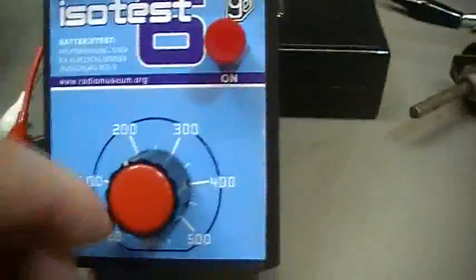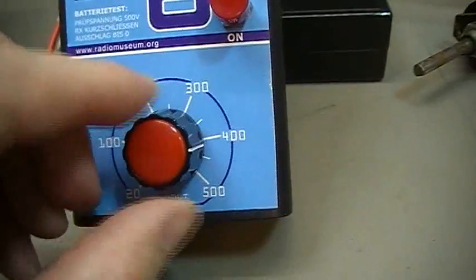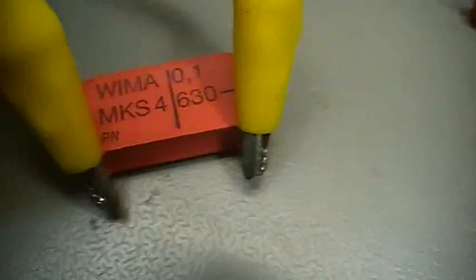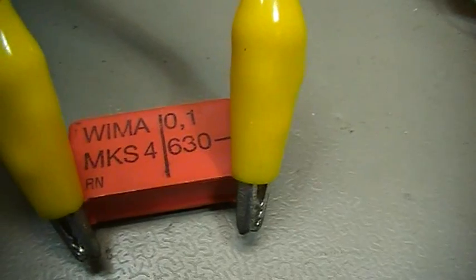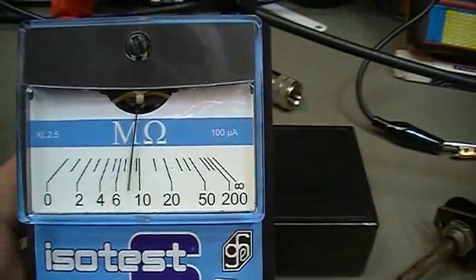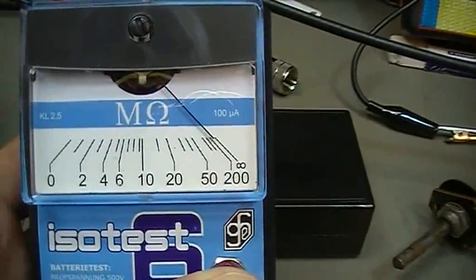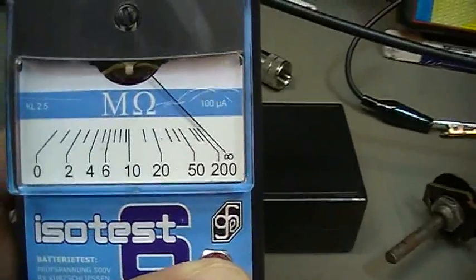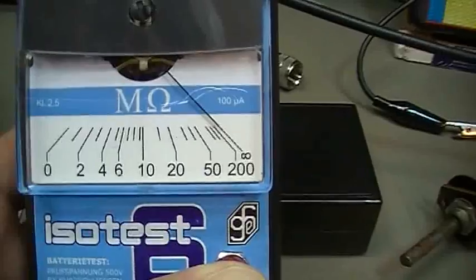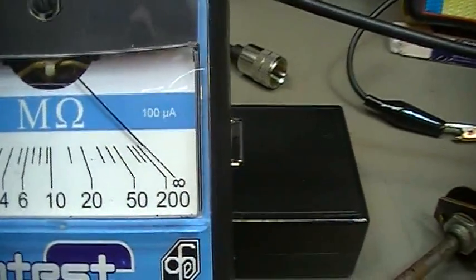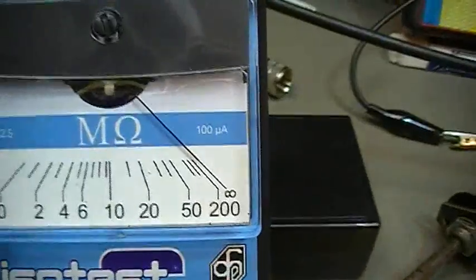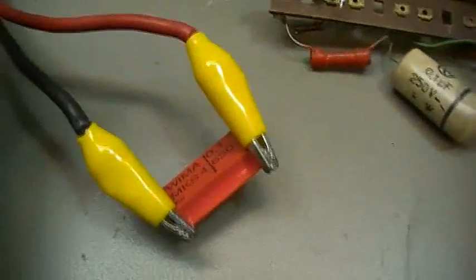What happens if I move my DC voltage up to 500 volt? This capacitor is able to take 630 volt, as you can read on the front. Same test with 500 volt DC - what can you see? We can see again the charging of the capacity, and that is exactly what we expect. The needle goes up to infinity, so we can be sure there is no leakage current at all.